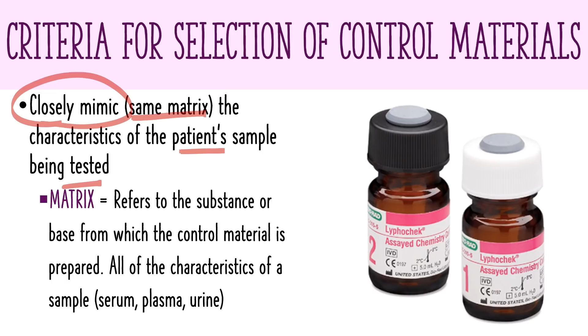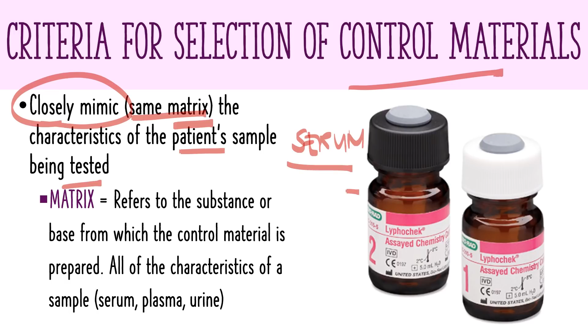So for example, if nandun tayo sa clinical microscopy, then most likely the machine is going to analyze urine. Then therefore, the control material must be the same as your urine. If sa hematology naman tayo, your control material must be the same as whole blood. Hindi naman exactly the same, but actually having the same matrix, or actually almost the same type of components. So if in case that your QC material is not exactly the same as the patient sample, then that is going to be a problem. So it is not going to be able to validate our procedure, mainly because your control material is not in the same matrix as your patient sample.